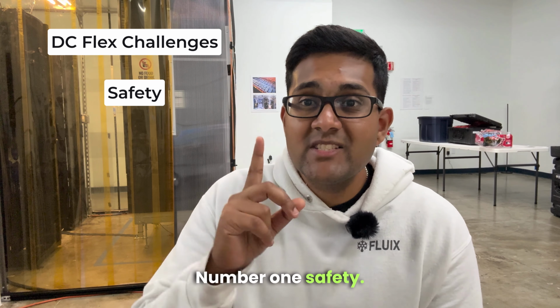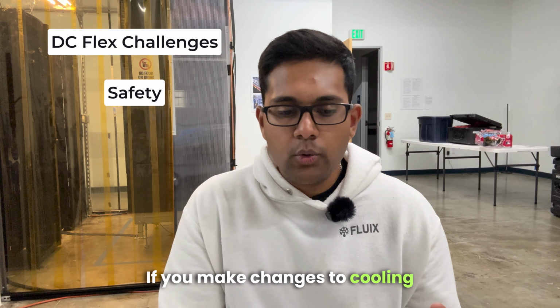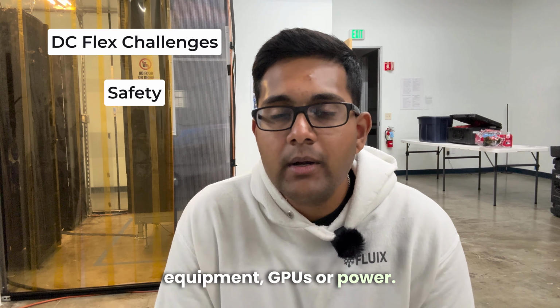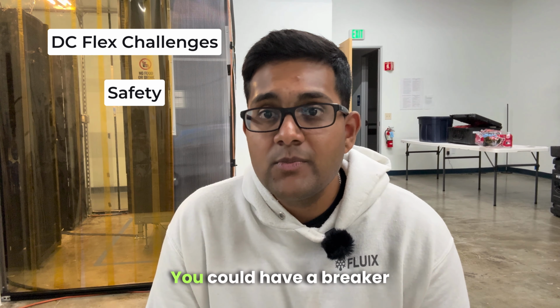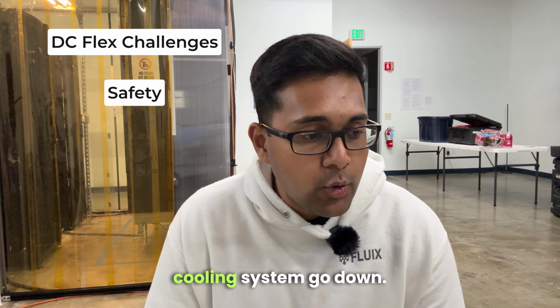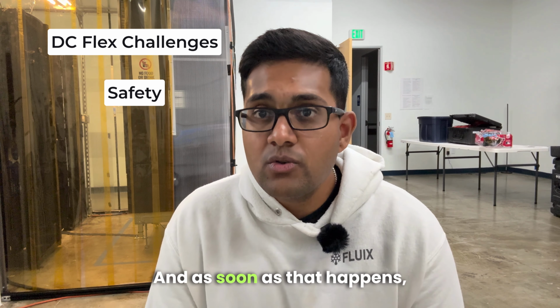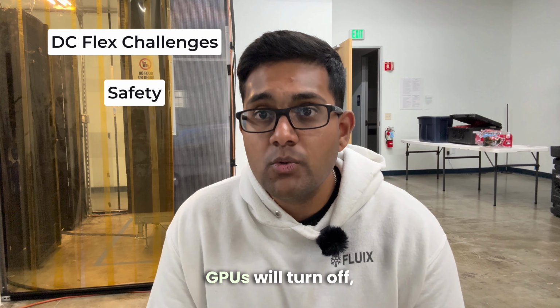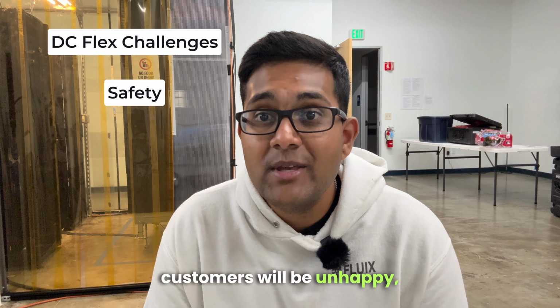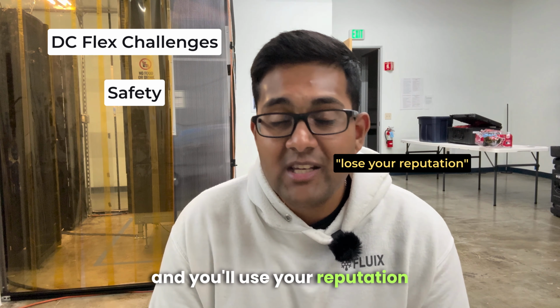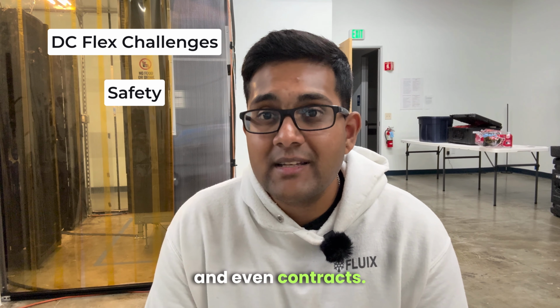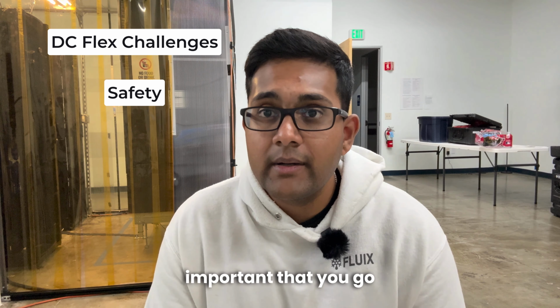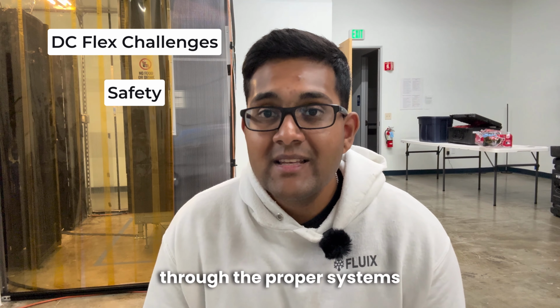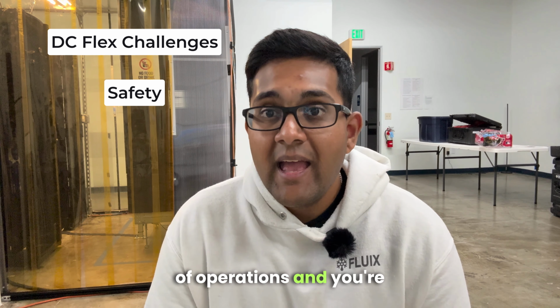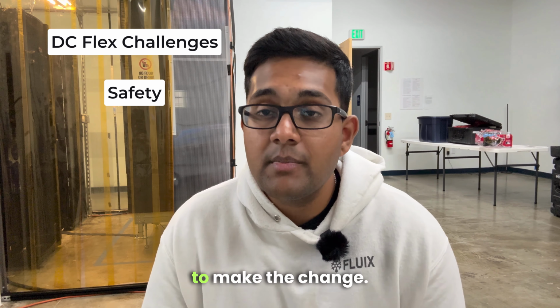Number one, safety. If you make changes to cooling equipment, GPUs, or power, there could be issues—a breaker panel could go out, a cooling system could go down. As soon as that happens, GPUs will turn off, customers will be unhappy, and you'll risk your reputation and even contracts. That's why it's important to go through proper systems of operations and understand when to make the change.